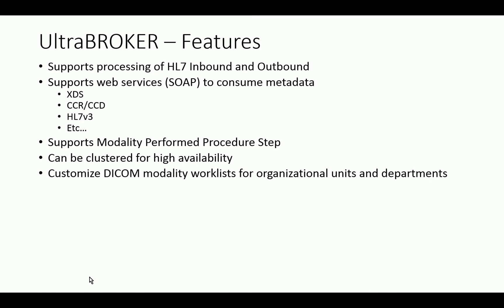Customize the DICOM Modality Worklist for organizational units and departments. When you implement an enterprise-wide broker, you have to support many different departments in many different organizational units. They could be in different locations, and there could be a lot of autonomy that those departments and locations have been used to with their current solutions. So you have to continue to support that type of autonomy even in an enterprise solution. We do have tools that allow you to do that, that allow them to customize the types of information that are returned to those modalities and the formatting of that data.